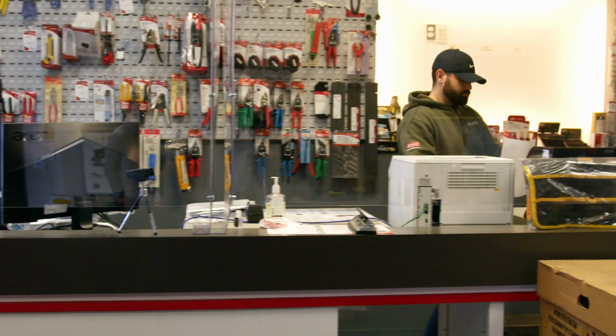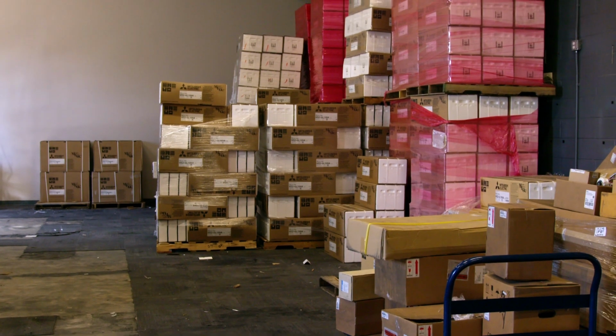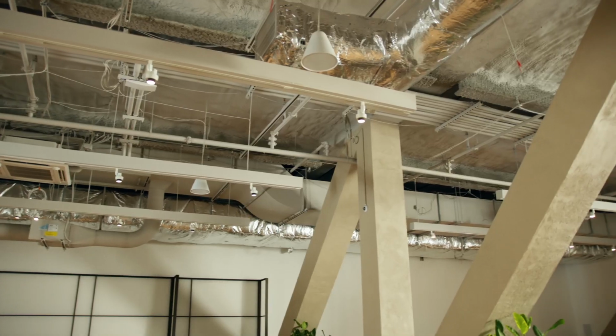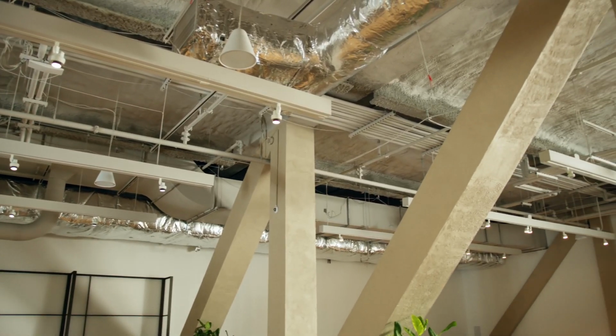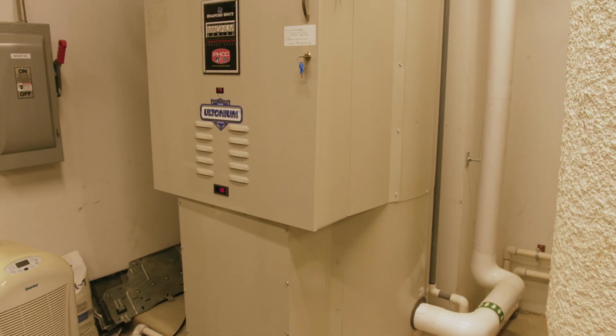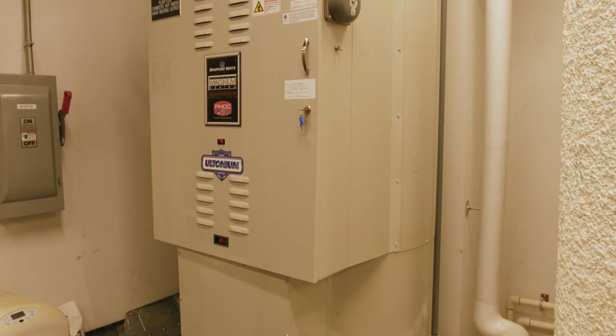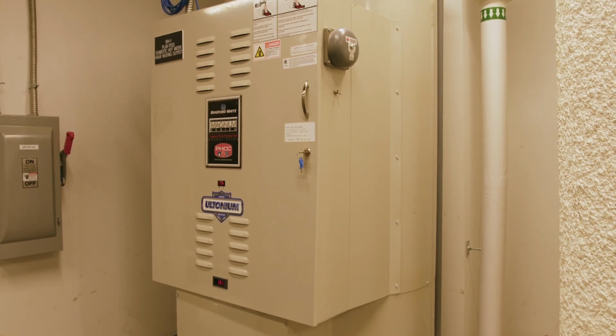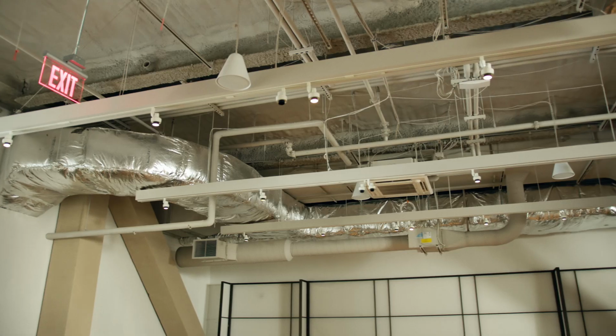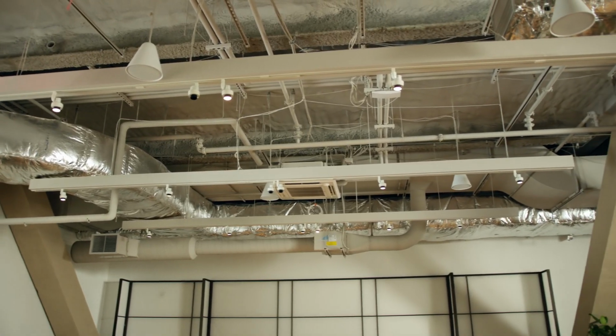My personal involvement with this project was to lay out all the ductwork, all the refrigerant piping, and coordinate that with the sprinkler, the plumbing, the electrical. In a building such as this historic building, the first floor really was a challenge because Hilton wanted to keep the 9-foot ceilings in this area, and the steel beams are right above that ceiling.